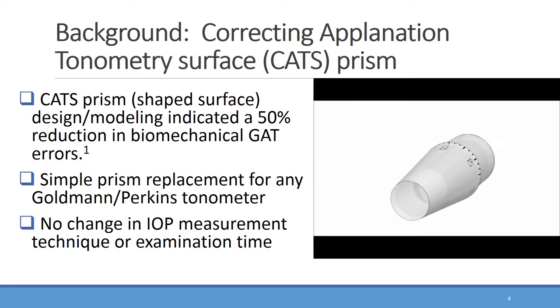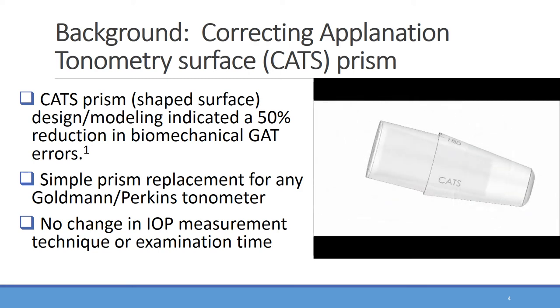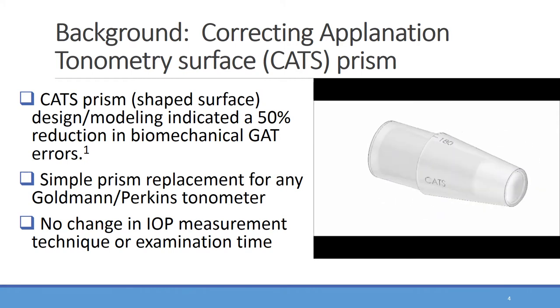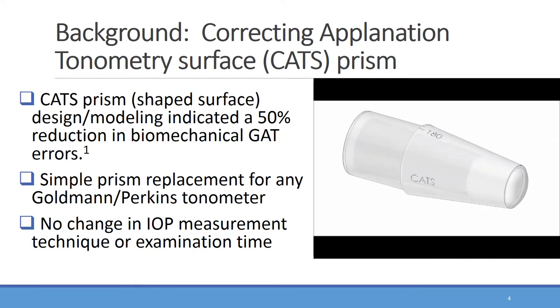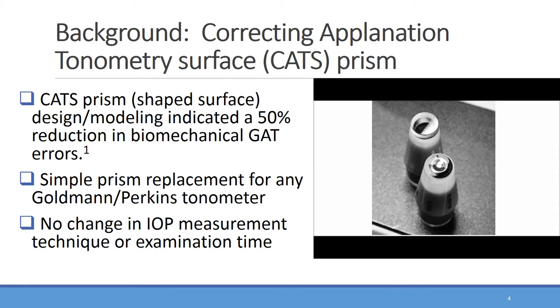As shown here, the Goldmann bi-prism has a flat contact with the cornea. The CATS tonometer prism depicted here is a replacement prism which fits any of the existing Goldmann or Perkins tonometers without recalibration or alteration in measurement technique or interpretation. The primary difference is the contact surface, which has a central concavity and annular convexity. This photograph demonstrates the difference in applanating surfaces — the flat Goldmann prism surface is in the background and the CATS prism surface is in the foreground.